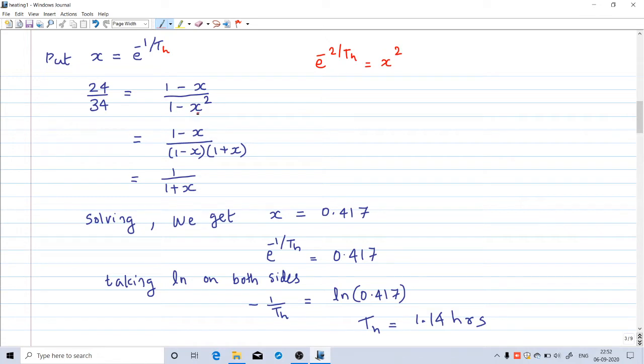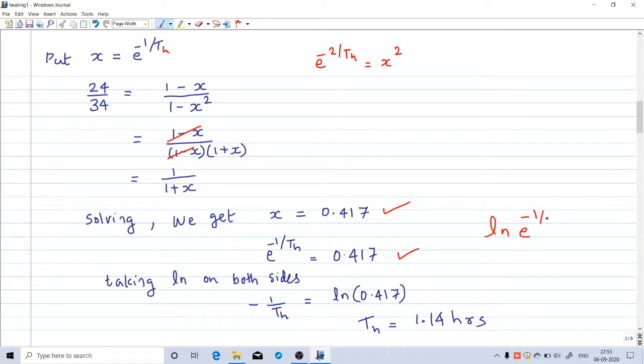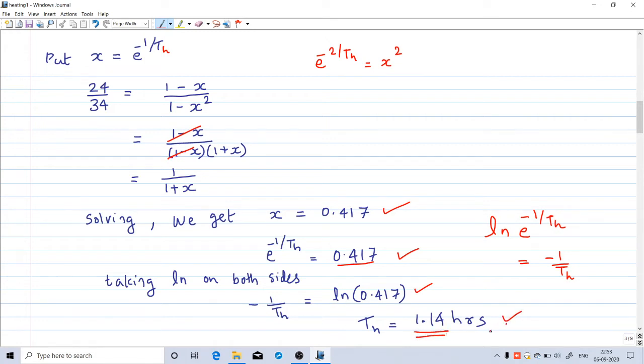The denominator 1 minus x squared can be written as (1 minus x) into (1 plus x), so the (1 minus x) terms cancel. We get 24 by 34 equals 1 by (1 plus x), and solving gives x equal to 0.417. Since x equals e raised to minus 1 by th, taking the natural logarithm on both sides gives minus 1 by th equals ln(0.417), and solving gives th equal to 1.14 hours — the heating time constant.